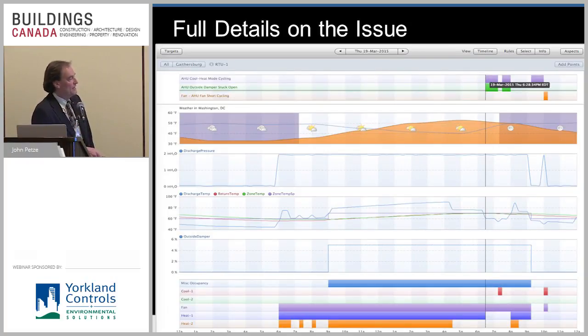Now, if we look at what else happened during the day, let's get familiar with this. The fan turned on at 6 a.m. and ran right through to the end of occupancy. Stage 1 ran almost all day. Stage 2 shut down around here. But look at what happened here, right around 6:50, 6:45 p.m., Stage 2 shut down, which is exactly when the conditions were detected.